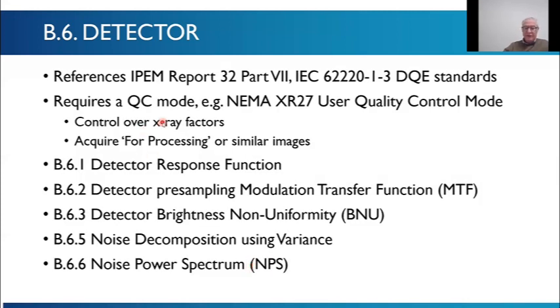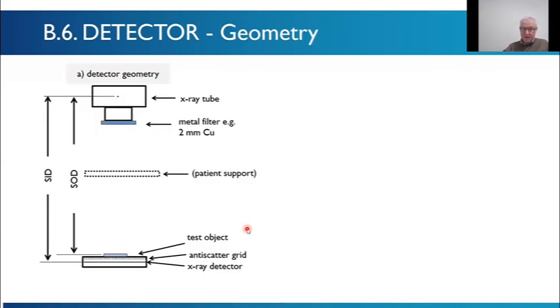To do this, you need a QC mode. So you need the NEMA user quality control mode, where you can set X-ray tube technique factors, and you can acquire for-processing images from which you can calculate. And then you measure these things like the response function, the MTF, the brightness uniformity, noise decomposition, for example, or power spectrum. These are all described quite carefully in the protocol, so I'm not going through them here. You need a nice clean geometry for this with metal filter, normally RQA filter or 2 mm copper or 1 mm copper or something like that. Put your test subject at the detector.